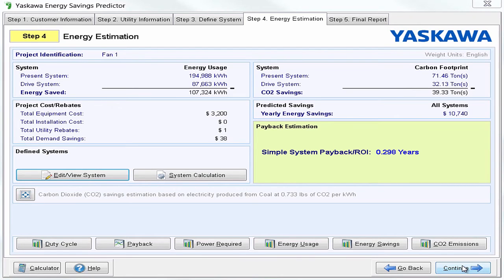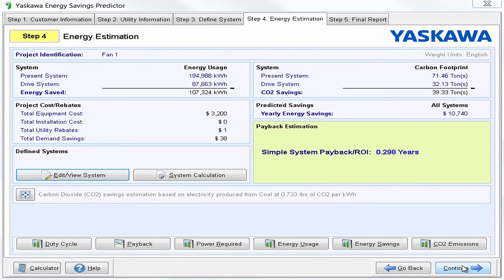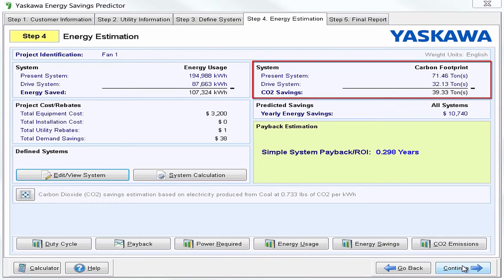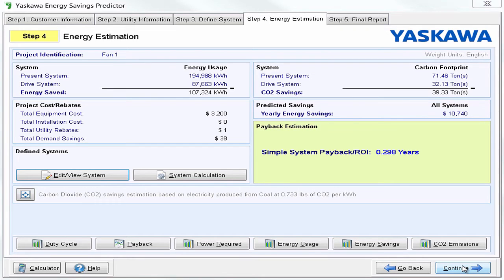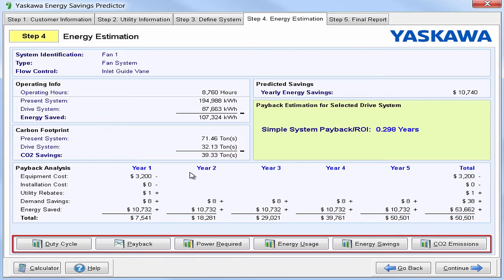Step 4 shows us our estimated energy savings. Our simple payback period came out to be 0.298 years. Remember, the system was running 24/7. You can see our energy usage before and after installing our drive system — we had a huge energy savings. Next, we can look at our carbon footprint: we saved 39 tons of CO2. You're able to go back and edit or view the system from the previous step, as well as view our system calculation. From here you can see our payback analysis over a five year period, and view those relevant graphs.